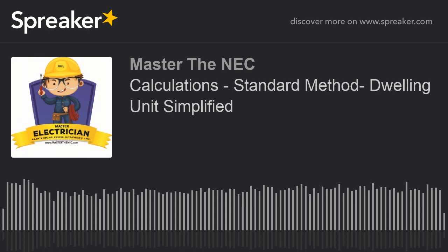We knew what our values were when we're dealing with our air handler, our air conditioner, and our condenser fan motor, right? We've already solved those. And those values are, let's see, remember the 1/4 horsepower at 115 volts for the air handler was 667 VA. The air conditioner compressor was a 5 horsepower at 230 volts.